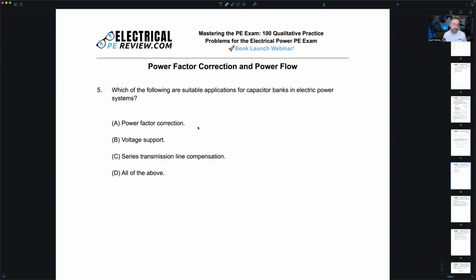If we're a large facility, large customer, have a lot of motors, we might have a pretty bad power factor, and the utility company might charge us a power factor penalty fee that in the long run is more expensive than, say, investing in large capacitor banks. Typically maybe there's a 3 to 5 year payoff period there. So that's power factor correction.